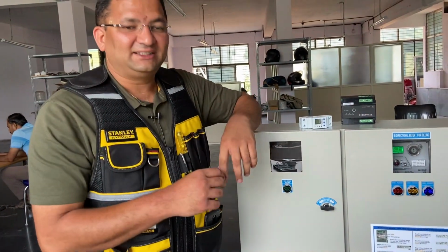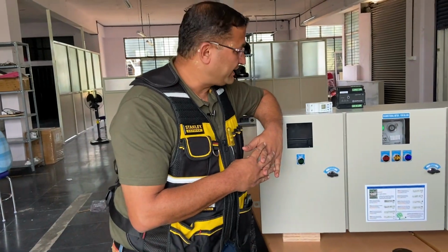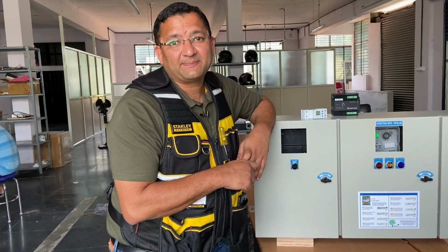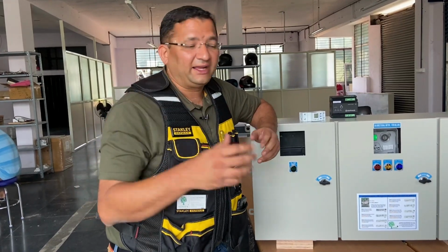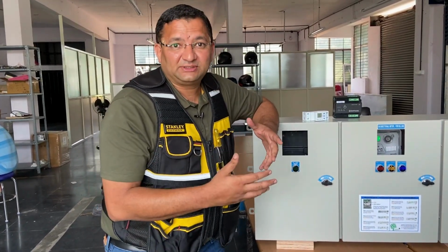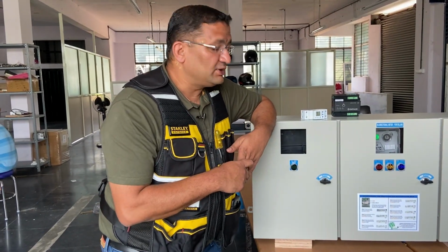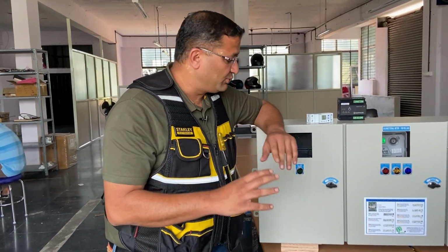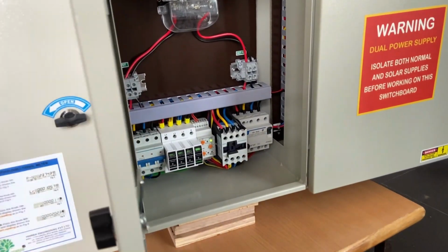So, I'll just put a small explanation about this relay and the contactor. Generally, in all protections or in all households, we use only the MCBs. MCBs generally sense the current and trip off after a certain high current. But in most of the inverter failures, particularly in the rooftop segment, we have a problem with high voltages. So, to sense and to cut the solar from the high voltage, we generally use a relay. As I showed you, this is one relay. This is on the solar side, and we also have it on the grid side.